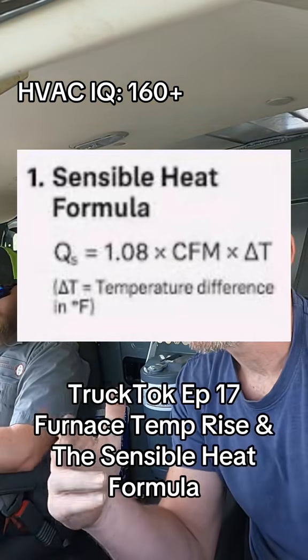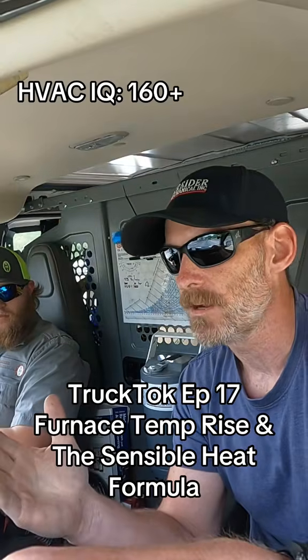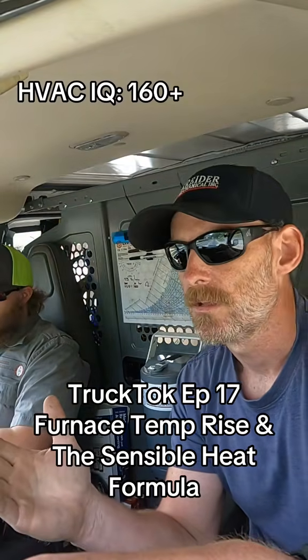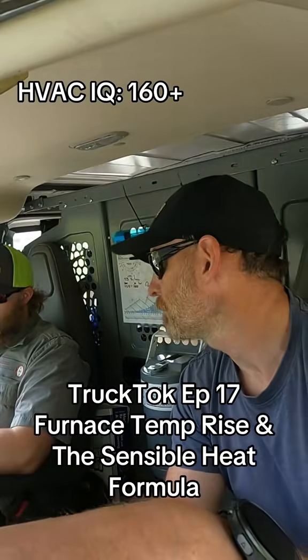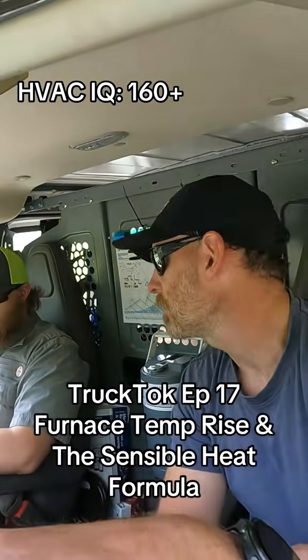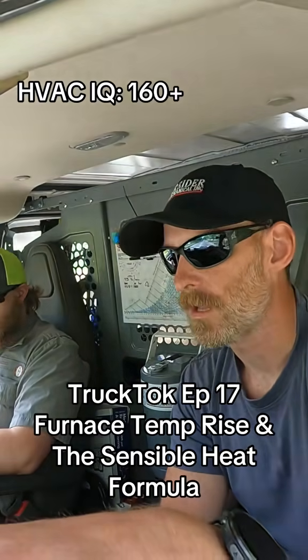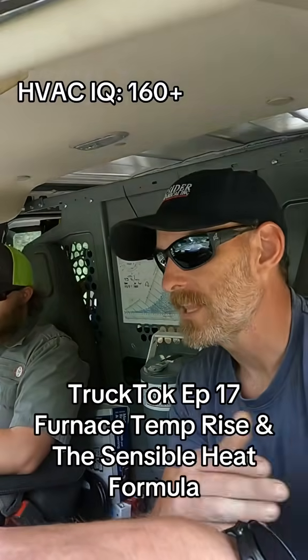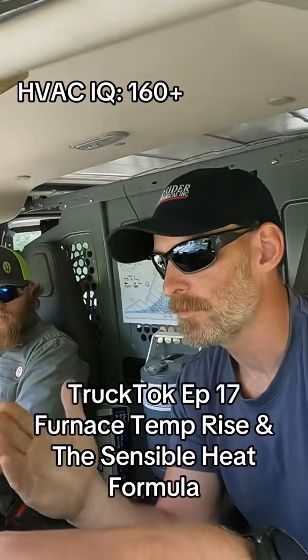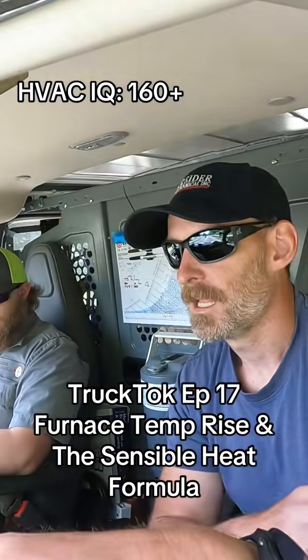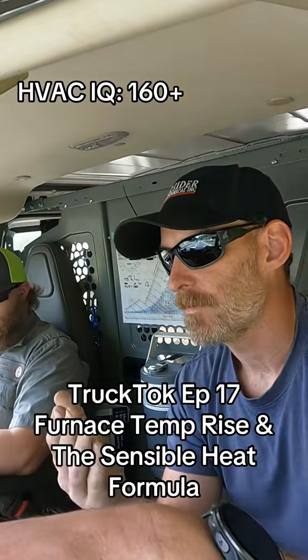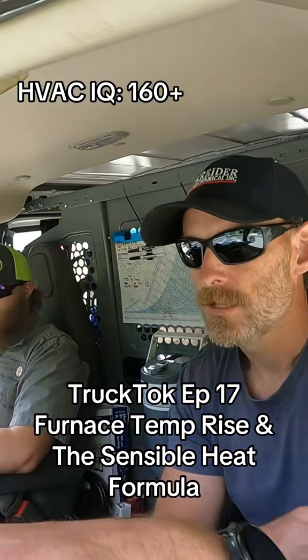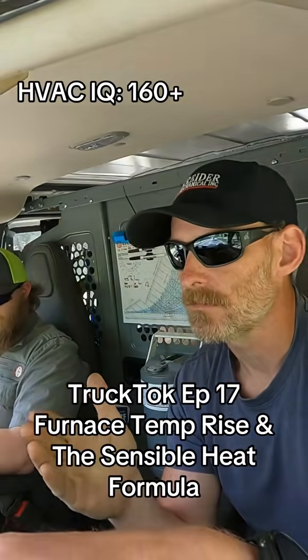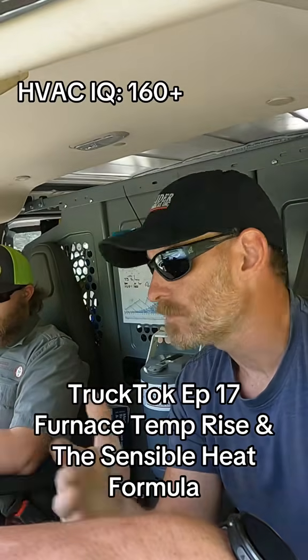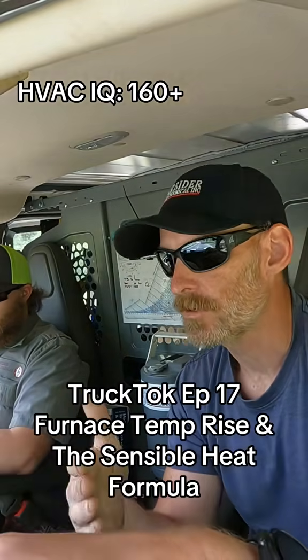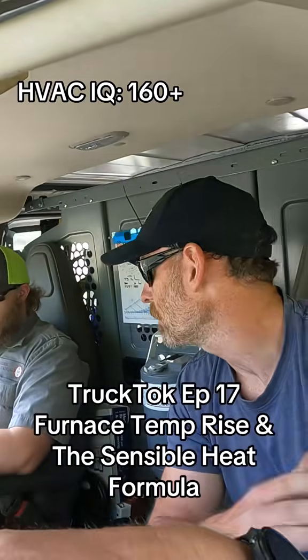And that 1.08 comes from the density of air being 0.075 pounds per cubic foot, and the specific heat of air being 0.24 BTUs per pound. And then they multiply that by 60 because you need to go from cubic feet per minute to BTUs per hour. And then when you multiply that by the temperature difference, you come out with the capacity, right? Okay. So they use that equation to calculate the temp rise. They just reverse that process in order to get a correct temp rise based on the correct amount of airflow.